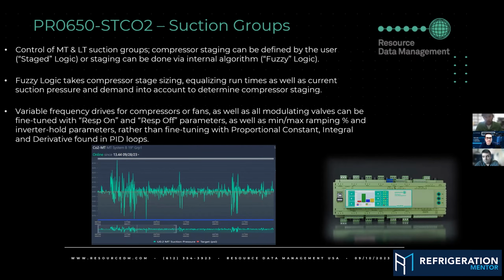Because here's the thing with these settings, like what Chris is talking about: response on and response off time at the case level, that's all great. It does make an effect, I'm not going to lie. But when you get into the transcritical portion, and you're talking about valving and high pressure and flash gas valves and everything else, I've walked into a controller that had these things turned all the way up to 60. I pulled my manual valve out, and it had lost its steps, because 60 is extremely fast on the response time.